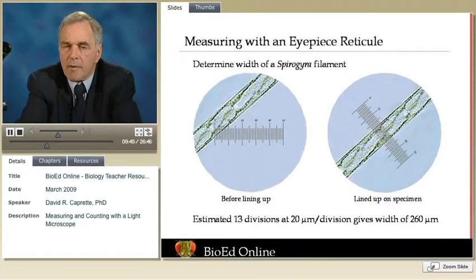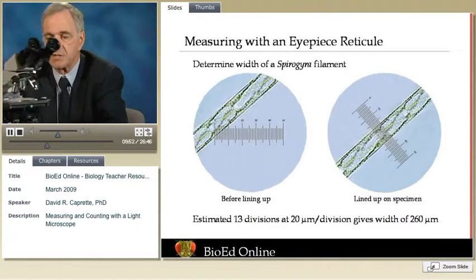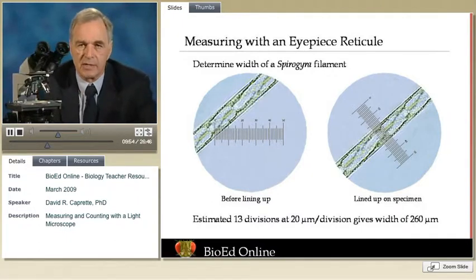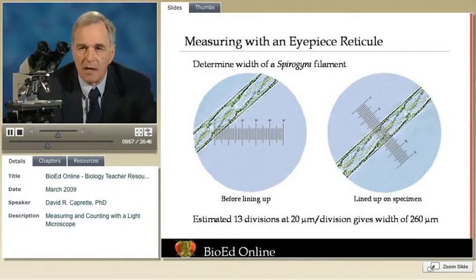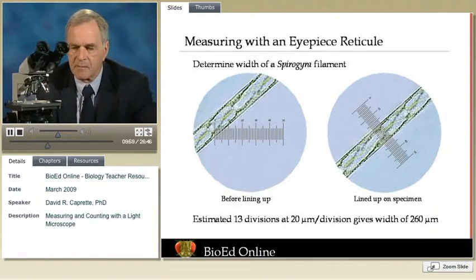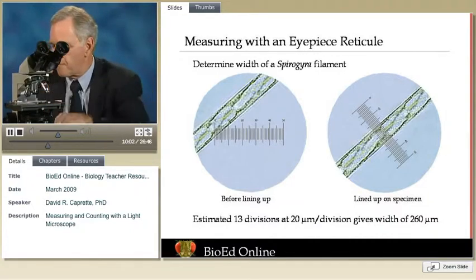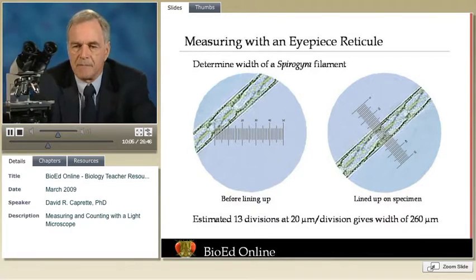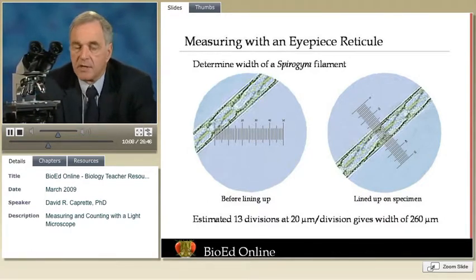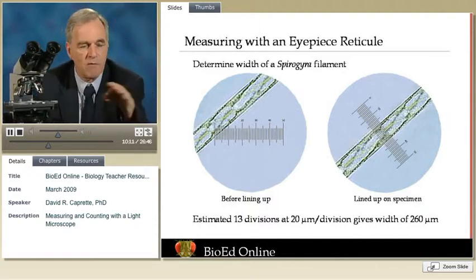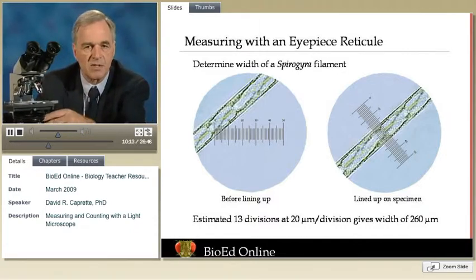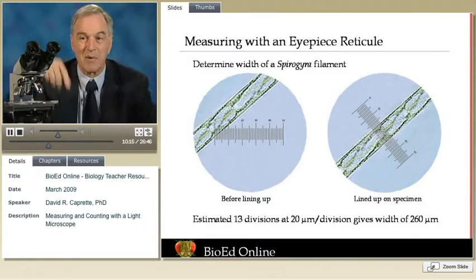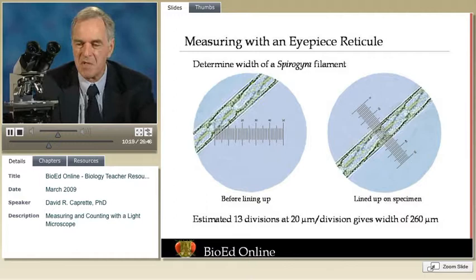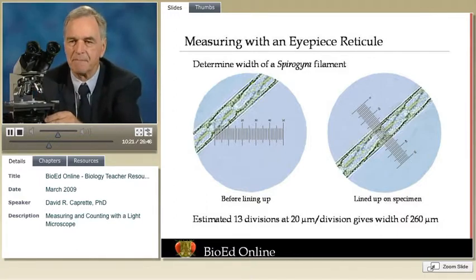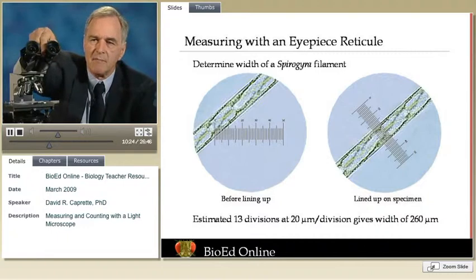Now let's see how we would go about measuring with it. Chances are the dimension you're interested in is not going to be lined up perfectly with your eyepiece reticle. It's probably going to be turned. It might be off-center. We have limited control over the position of the specimen. We can move it around by manipulating the stage, but we can't rotate it. But we can rotate the eyepiece itself. So we center up our specimen, and then we rotate the eyepiece until the scale crosses whatever dimension we want to measure.